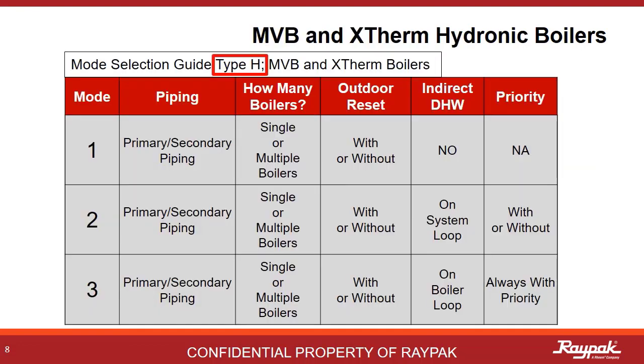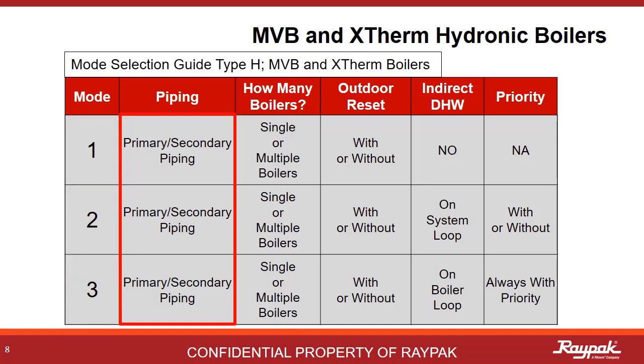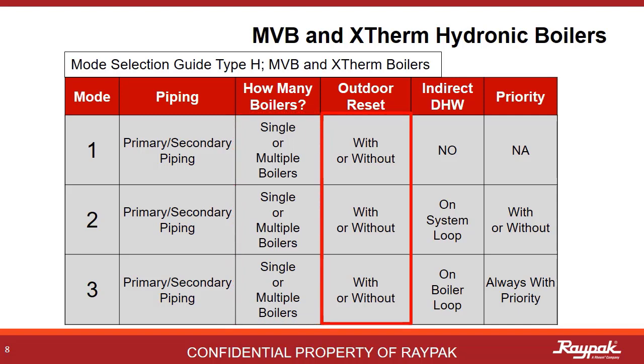This is a summary table for the hydronic type boilers. There are three modes to choose from: Mode 1, 2, and 3. All must be plumbed primary and secondary, as the MVB and X-Therm boilers are low mass. All three modes can be applied to single or multiple boilers, and all can run with or without outdoor reset. The difference lies in the presence or absence of an indirect hot water system. If there is no indirect system present, then it is a Mode 1 — this is the most common configuration.